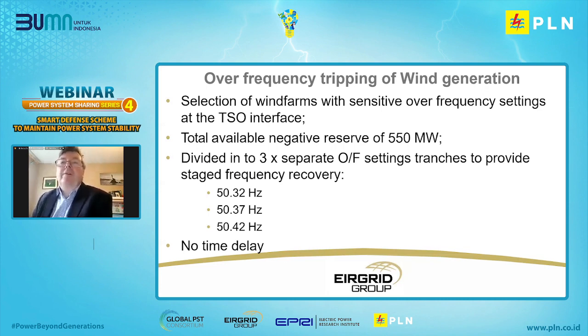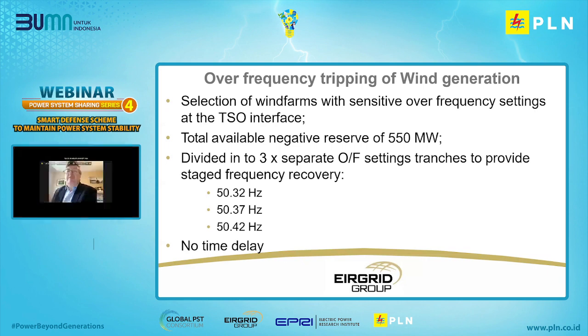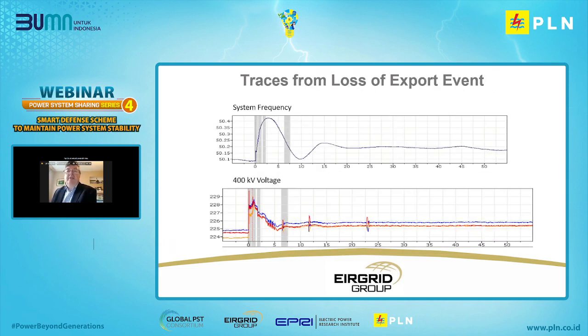So the over frequency tripping of wind generation: we can select wind farms. We are keeping a total negative reserve of 550 megawatts, which is the max import and the max export on the interconnector. And the wind farms are then tripped on 3 separate tranches of over frequency, 50.32, 50.37, 50.42. And there are no intentional delays set on these. Okay, next slide, please.